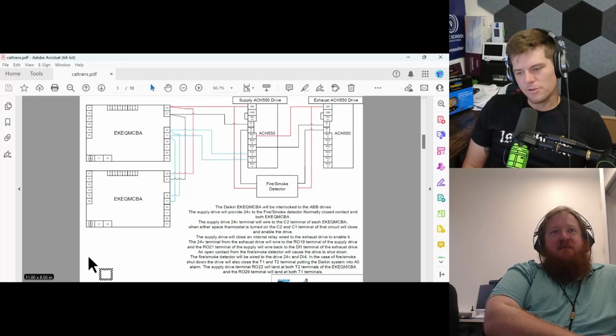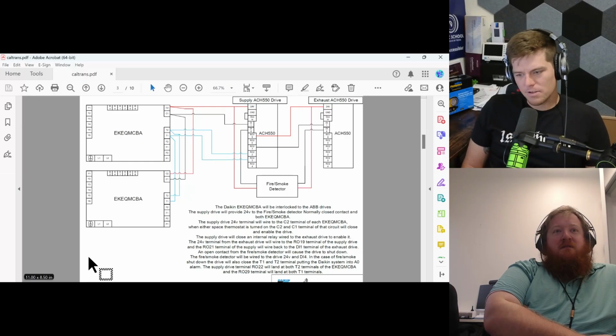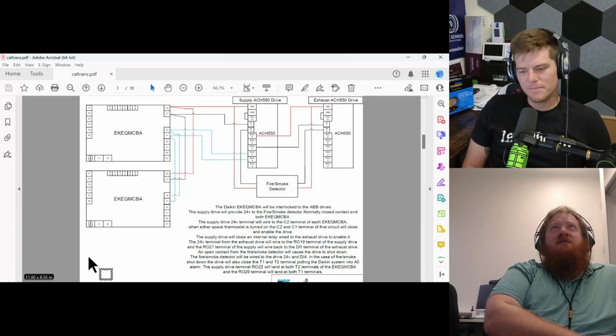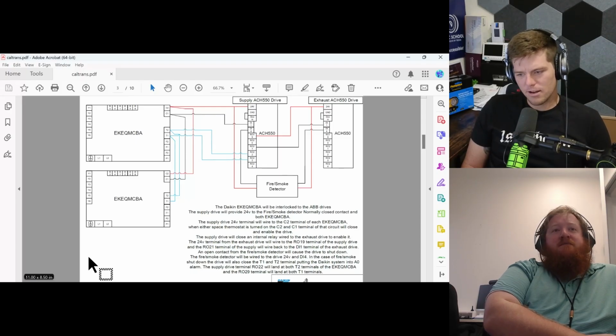What about parameters - are you changing parameters to energize the relays you're talking about, or are those already E-stops in themselves? It depends on the macro you're using on that drive, but DI4 is always the start/stop or the emergency. As long as that's set, you can go in and change the relay outputs to do whatever you want, making sure it's set to auto reset. That's the biggest thing I always find too.